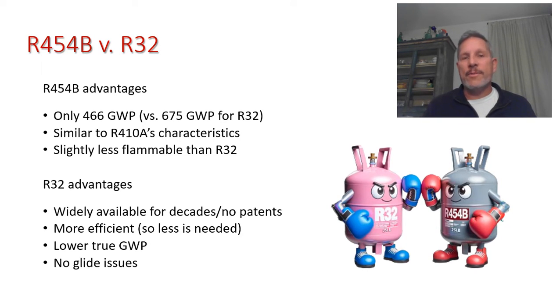There is a concerning factor with both new refrigerants: they are A2L refrigerants. A3 is the most flammable — like propane — while previous refrigerants like R12 and R22 were A1, not flammable at all. These new refrigerants are slightly flammable. R32 needs 14% concentration in the air to ignite, and R454B only 11%. However, once ignited, R32 is more propagating of the flame.